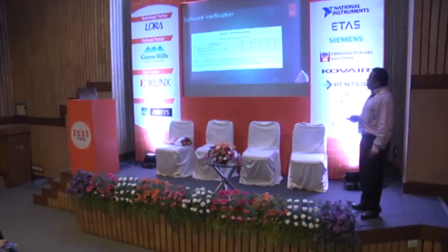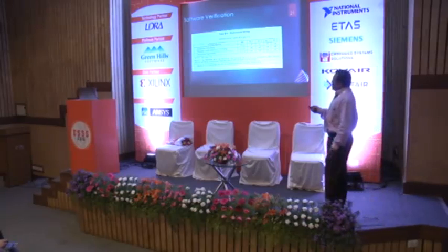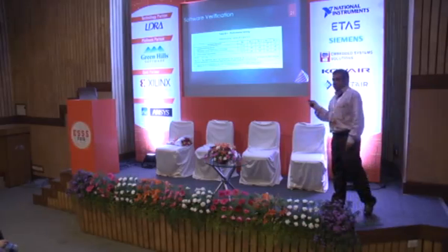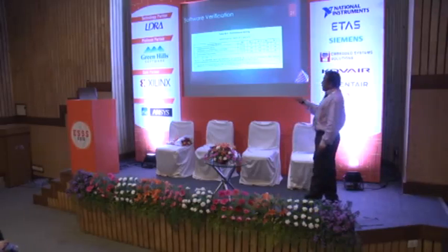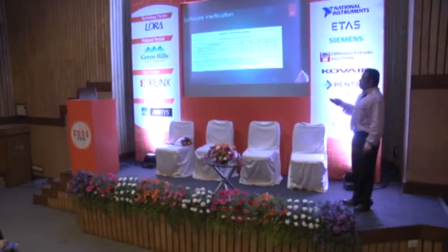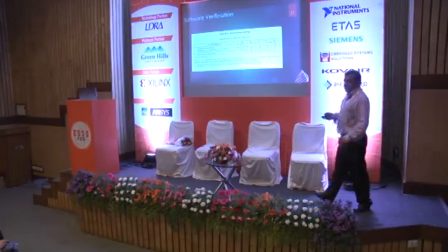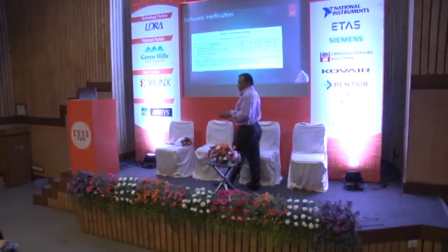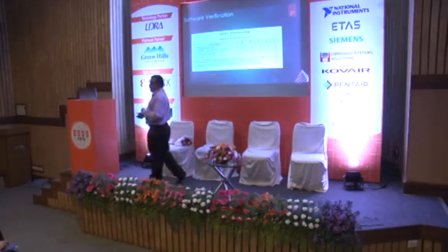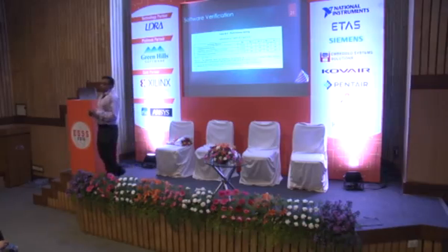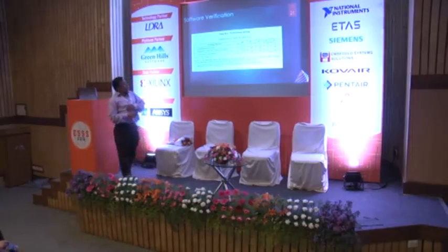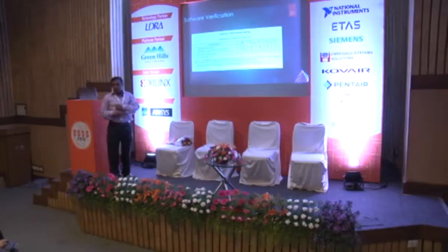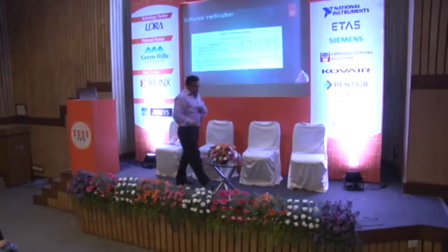This is one example from Table B for performance testing: response timing and memory constraints. No options are given to the project team. Irrespective of the skill levels, you have to do performance testing for response timings and memory constraints. Whereas for avalanche or stress testing, which means my software can handle, let's say, 32 channels, do you really want to flood and test whether it can really handle 32, or what happens when all 32 are talking to you simultaneously? Maybe you have an option for SIL 1 and 2, but not for 3 and 4. That's how you read and interpret the standards here.